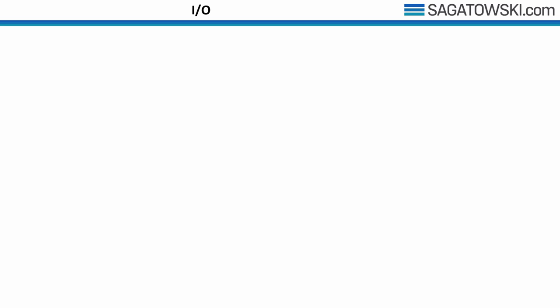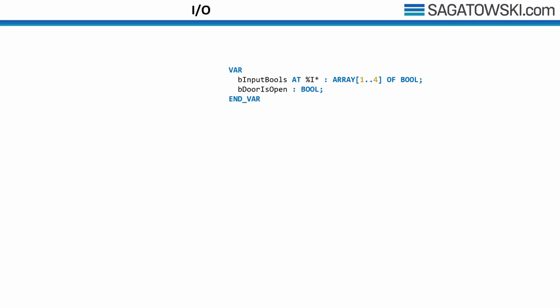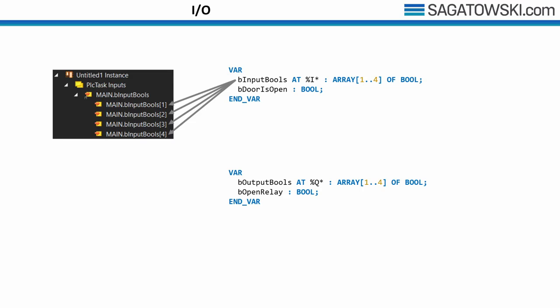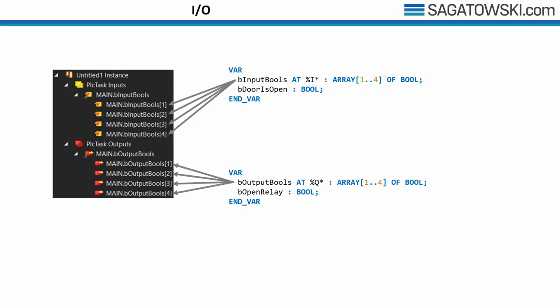To use fieldbus devices in TwinCAT you have to link the software to the hardware. For inputs, this is defined with the %I* characters and the data type of the inputs. Compiling gives you instance variables in the process data image that you can link to the hardware. For outputs it's done the same way, with the only difference that you use %Q* instead. Once this is done, you can freely use these variables in your code.